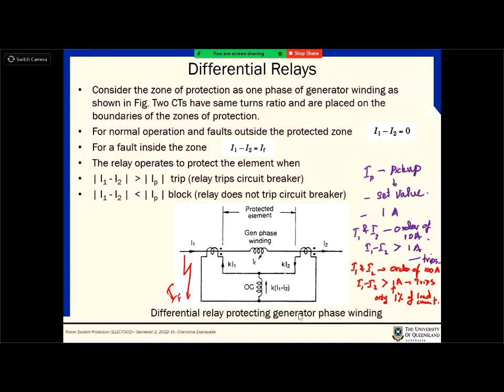It's the same, right? Still I1 minus I2 is 0. Why? Because you are outside the protected zone. So with this technique, you can clearly define the boundaries. The boundary is from this CT to this CT. That's what is written as the protected element. Can you see that? So it's in between those.